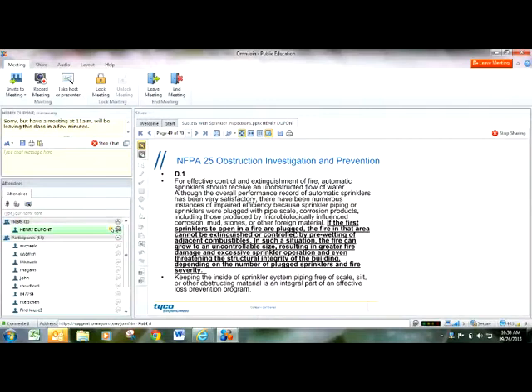So if you've got a severely obstructed sprinkler system and the first sprinkler head fails to open and that fire continues to grow, additional sprinkler heads are failing to open, or more heads are trying to operate than the system was designed to operate at once, the fire can grow out of control and it can threaten the structural integrity of the building.